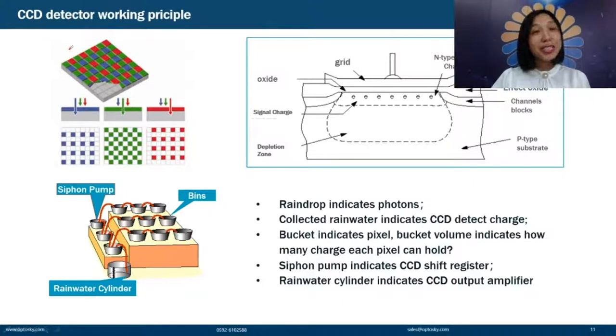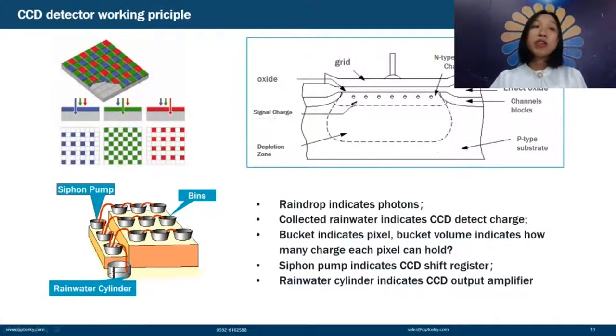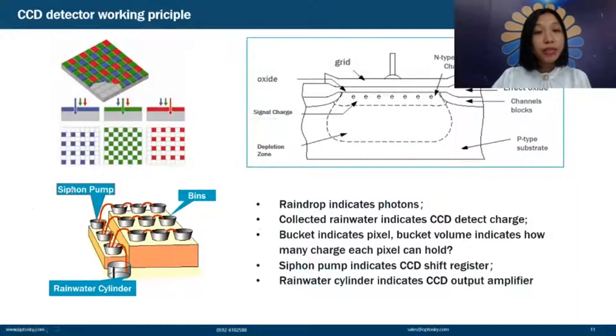Next, we introduce the CCD detector. The detector determines the most significant cost of a spectrometer and is a very important component. When a photon strikes the detector, it generates ionization and charge accumulation. We will use a vivid analogy to explain the detector's working principle.